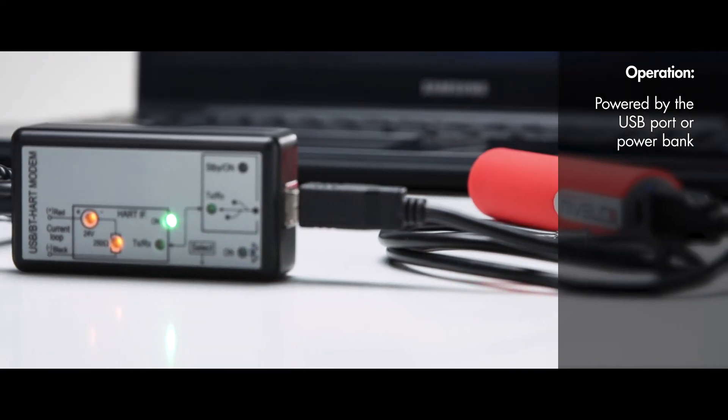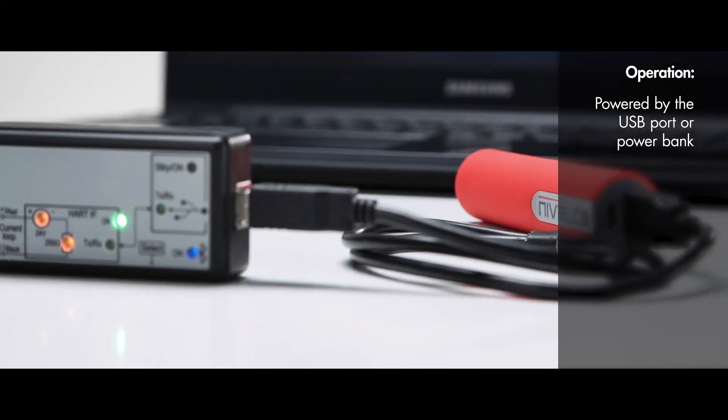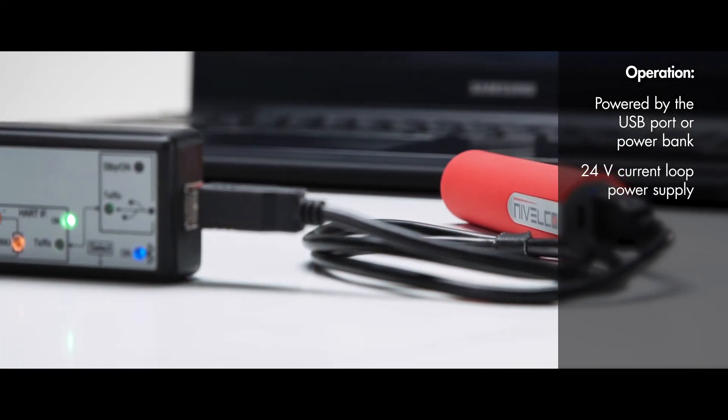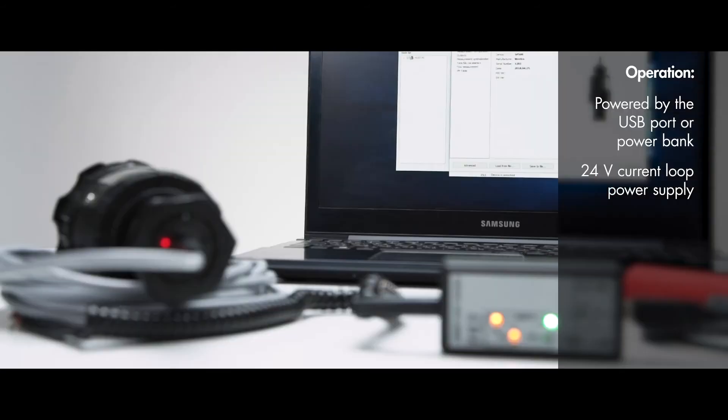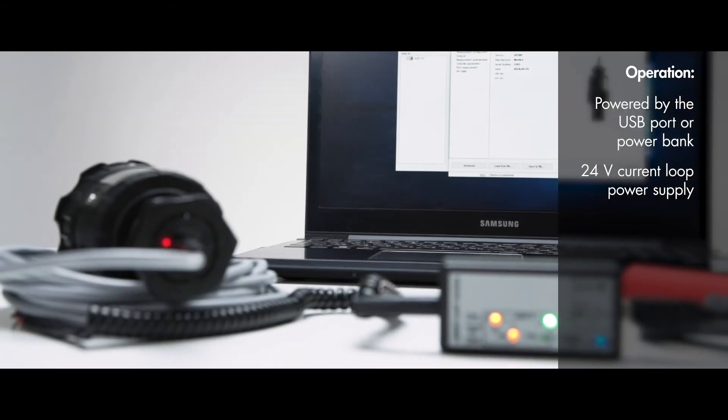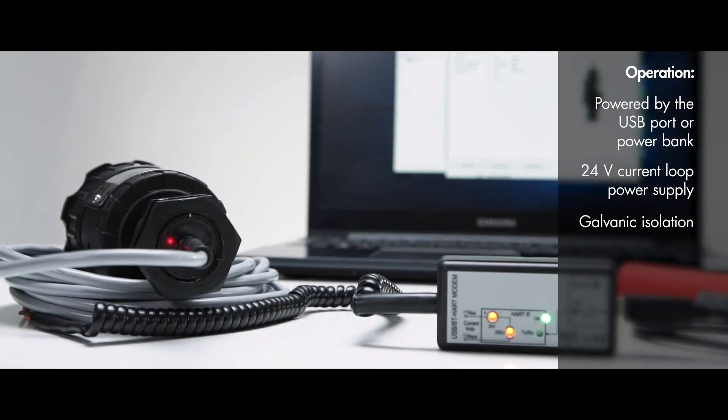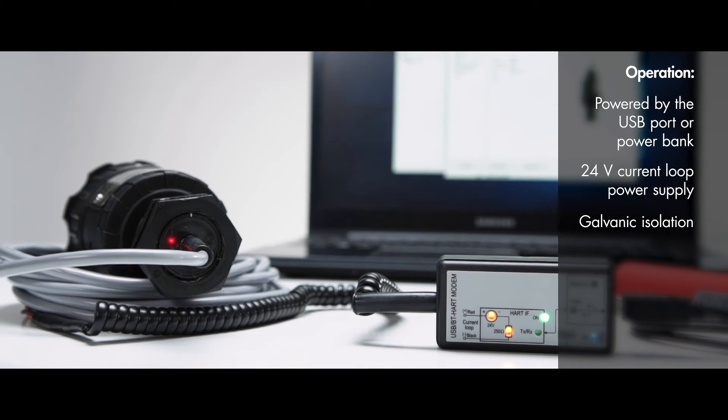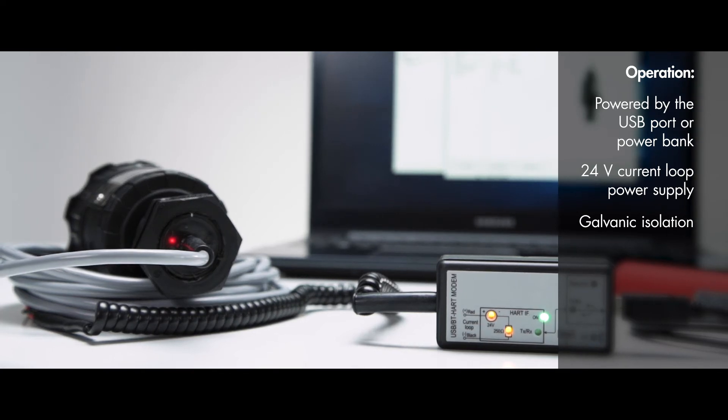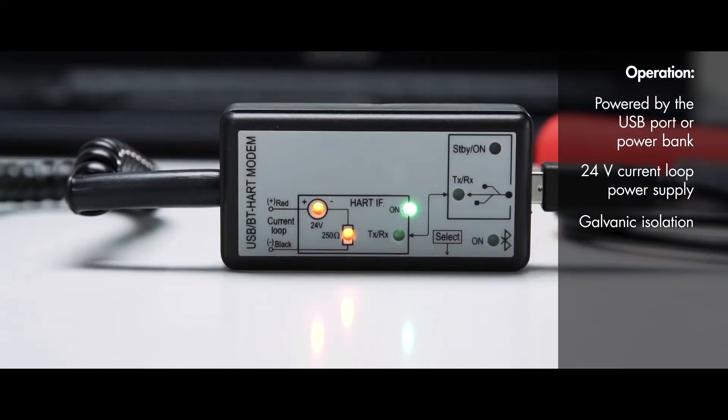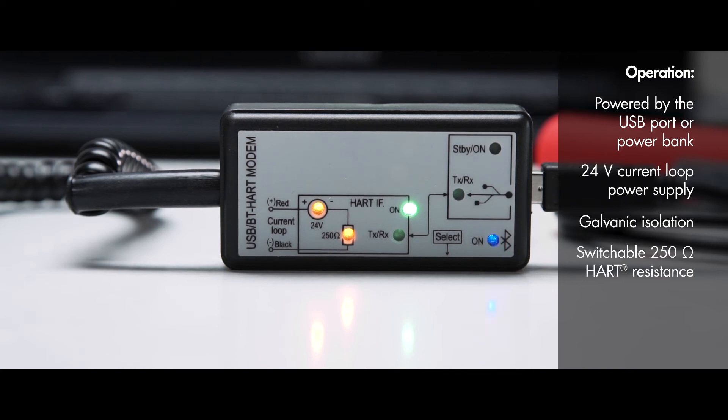A very useful feature of SAT-504 is that it can supply power to the HART loop, so if necessary, the transmitter connected to the loop will receive power supply from the modem. The 24-volt DC transmitter supply option can be switched on and off on the device.